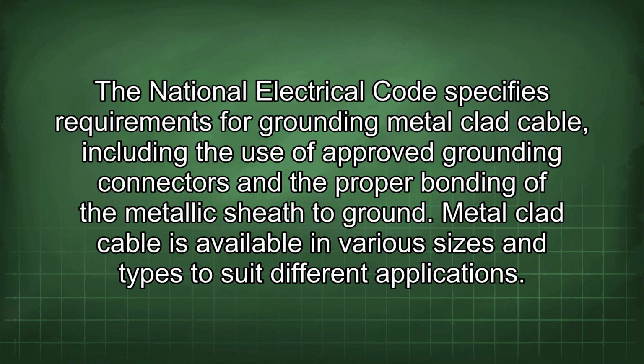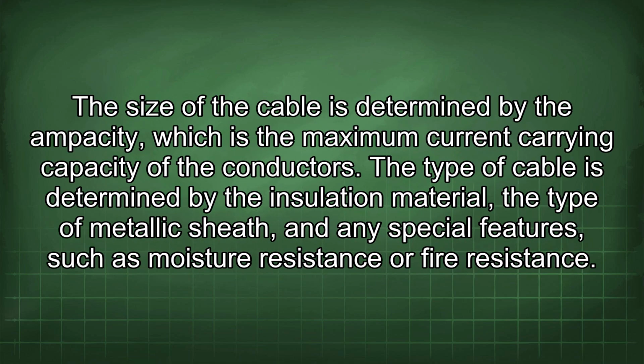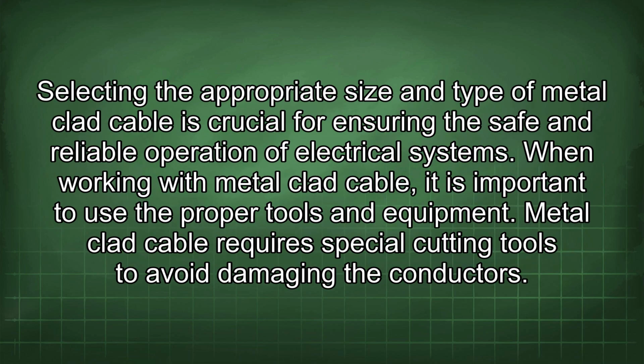Metal-clad cable is available in various sizes and types to suit different applications. The size of the cable is determined by the ampacity, which is the maximum current carrying capacity of the conductors. The type of cable is determined by the insulation material, the type of metallic sheath, and any special features such as moisture resistance or fire resistance. Selecting the appropriate size and type of metal-clad cable is crucial for ensuring the safe and reliable operation of electrical systems.